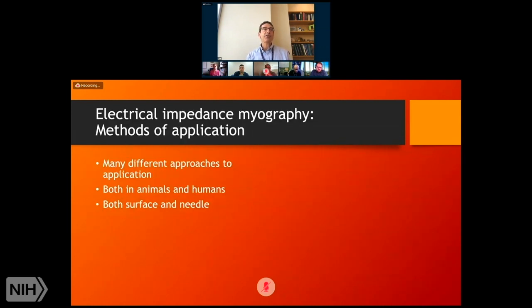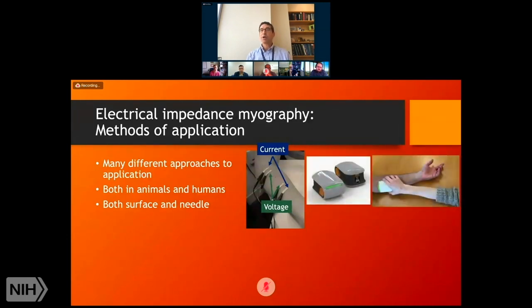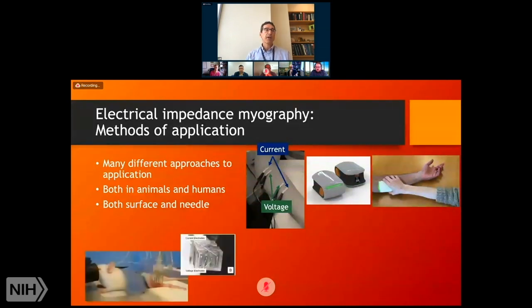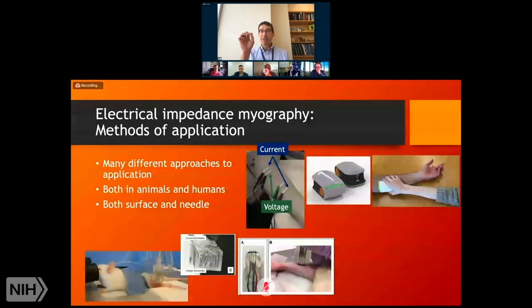We've had a number of different applications for this, both in animals and humans, using surface and needle electrodes. The basic setup uses outer electrodes to apply current and inner electrodes to measure voltage. A newer system has all of this within a single device applied to the skin. In mice we use a metal grid with the same current and voltage electrodes, removing fur with Nair and placing it on the skin. We also use needles in mice and rats — a four-electrode needle array. While fur causes some challenges with contact impedance, using tiny needles that just puncture the skin allows us to get beautiful data.